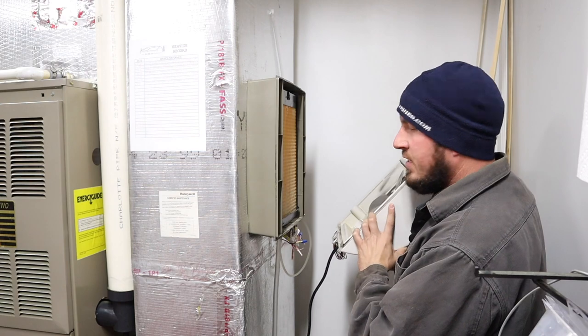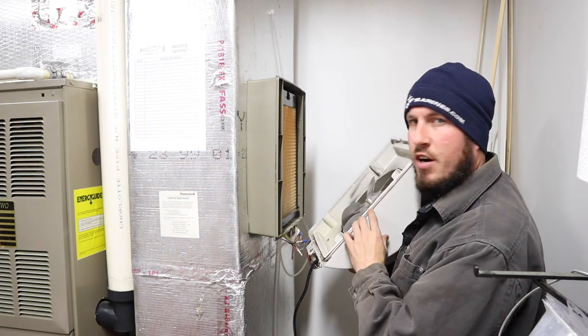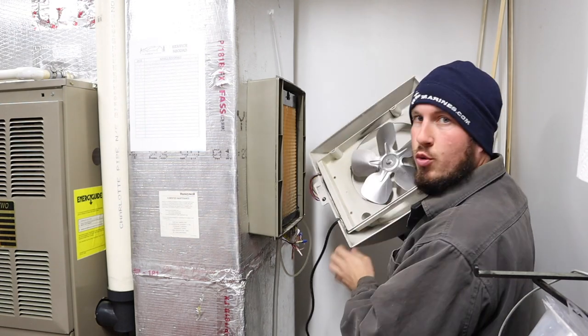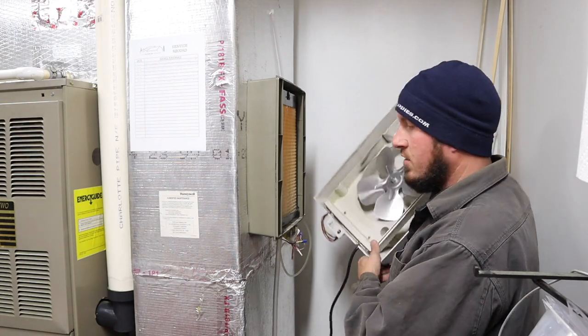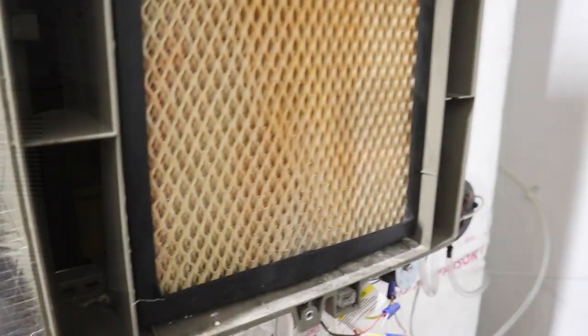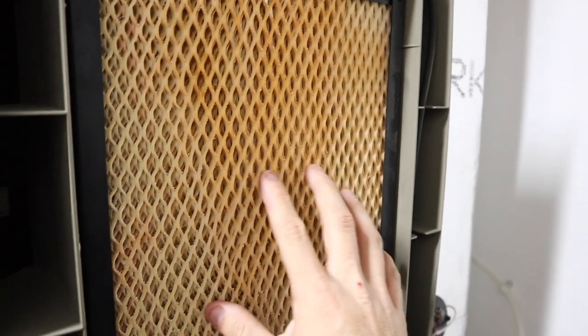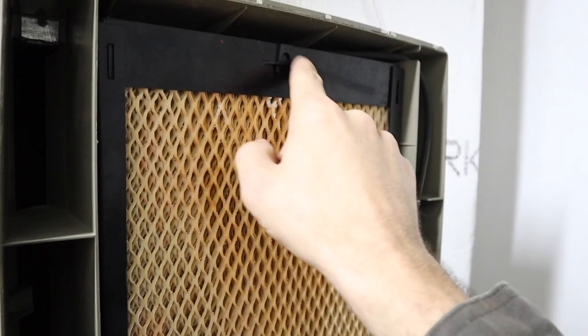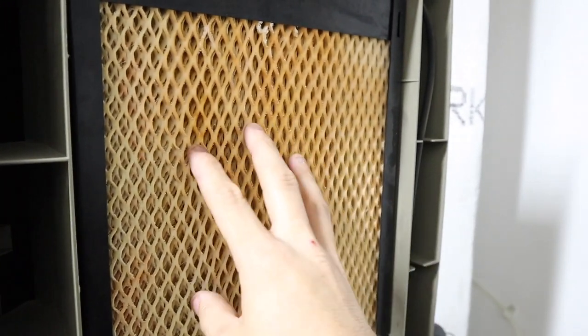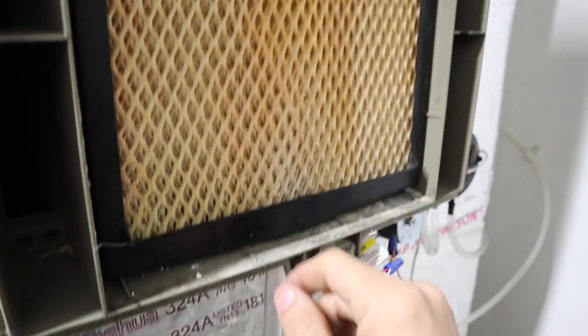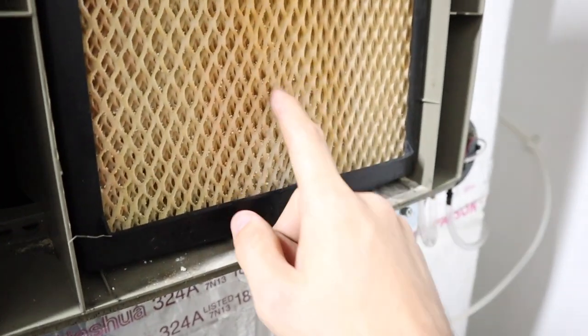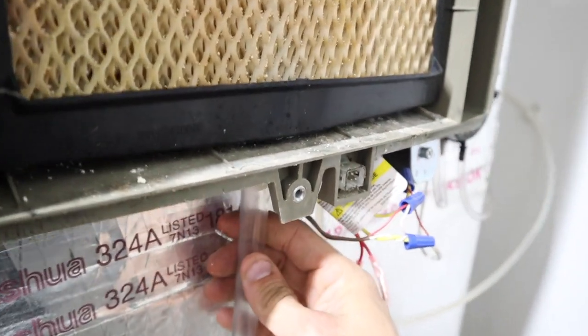There's no water line connected to your cover. It's just your actual plug here that's connected. So you can go ahead and put that down. You want to replace this pad. So this pad is an evaporative pad that literally gets water trickled down over it and then your fan just pushes the air through it. So the key to taking this out is first taking your drain tube off.